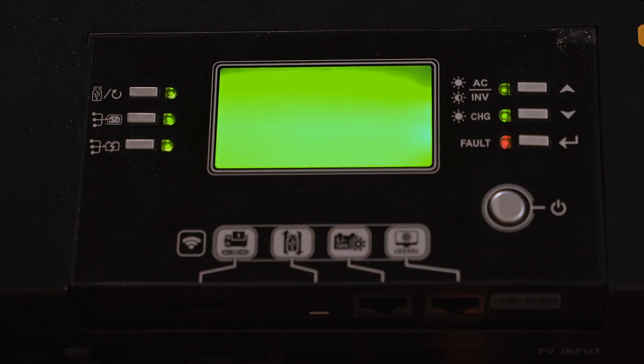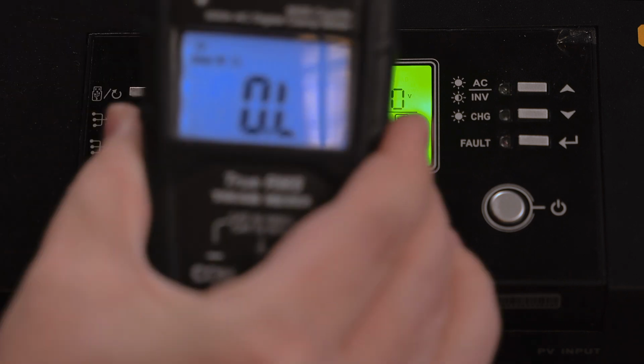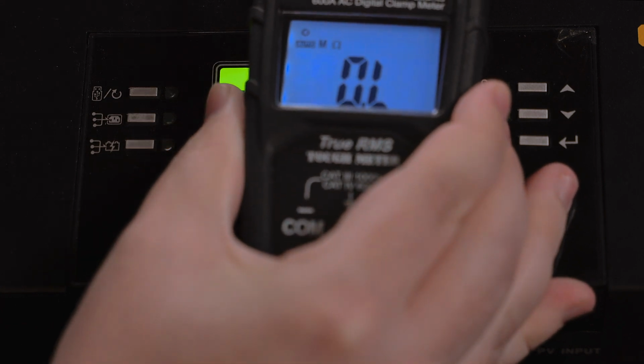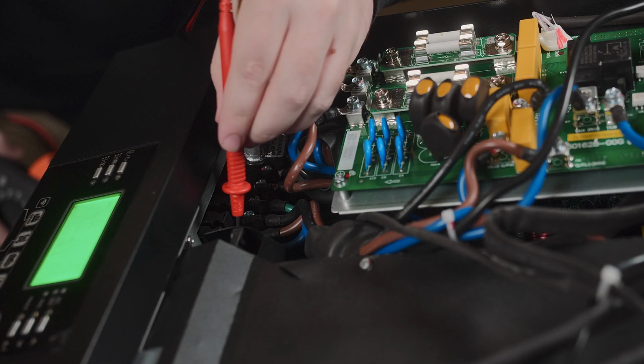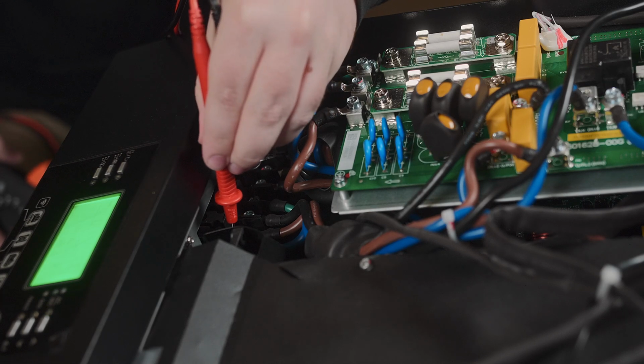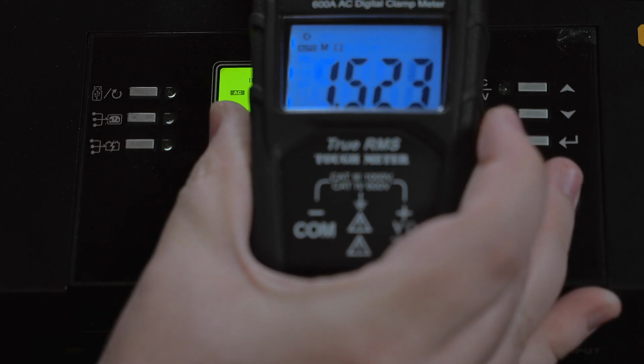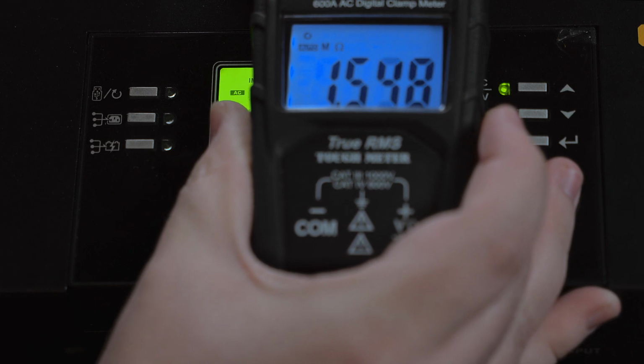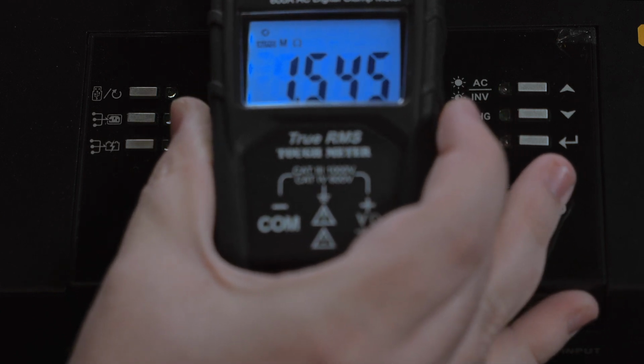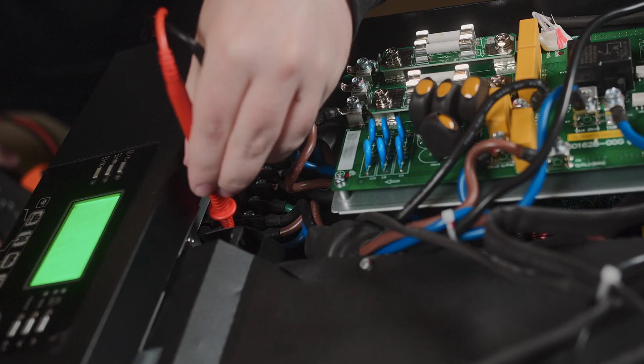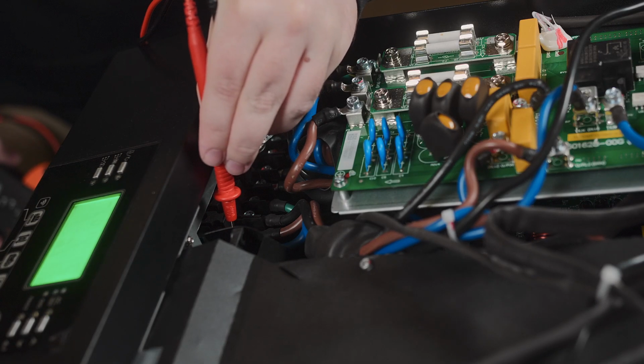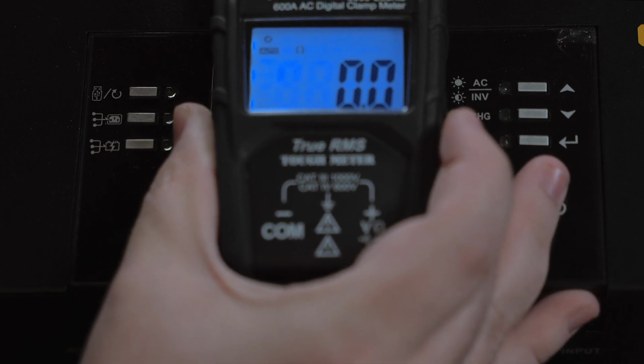Alrighty, we're able to turn the unit back on now, and it will save the enable the bypass on setting 34. Once we've got that, let's throw our meter back up here and check from neutral to ground. We got about a mega ohm and a half, effectively open. That's such a high resistance that it effectively is open. And then let's check our neutral to neutral. Now we have continuity there. So the neutrals are always going to be shorted.